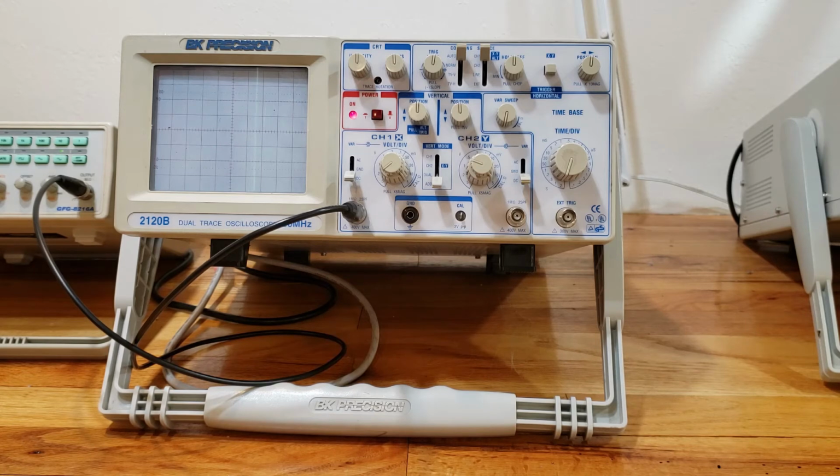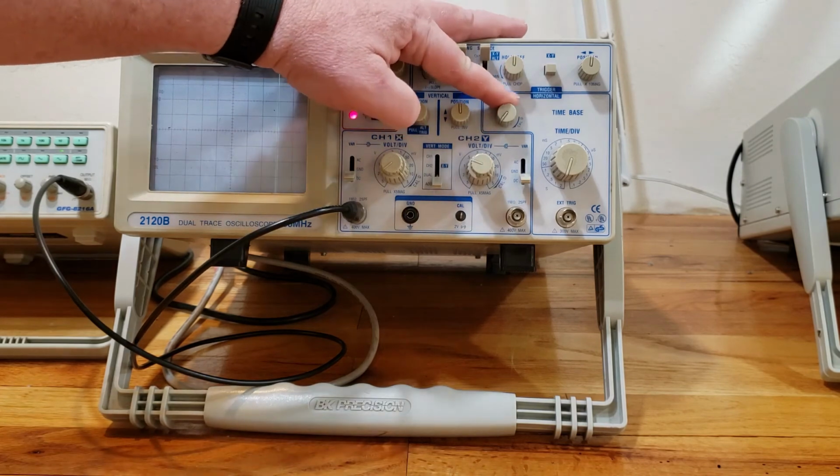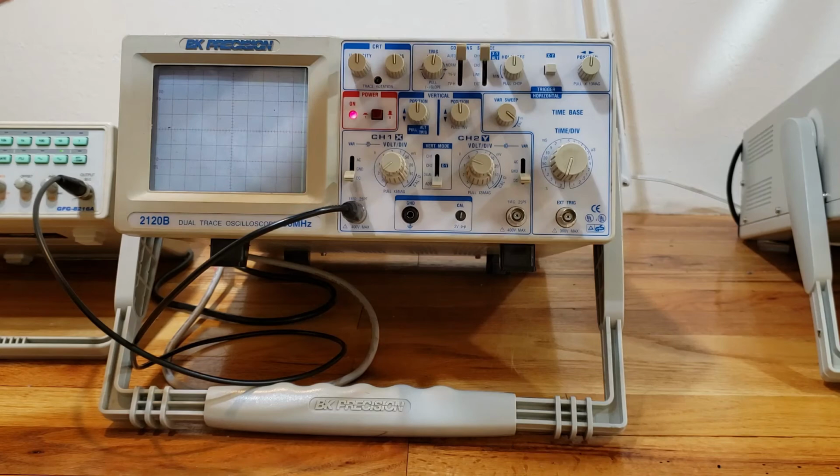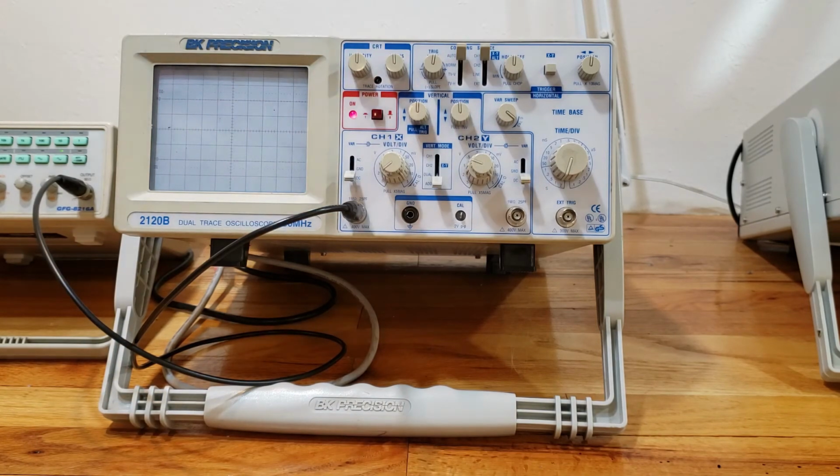So what do we do with it? Well, I'm glad y'all asked. Here's what I'm going to do with the variable sweep knob. I'm going to turn it clockwise all the way to the right so that the indicator points down toward the time division knob. All right? Remember, do not center the variable sweep knob.